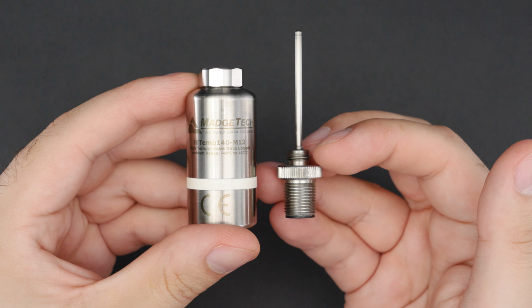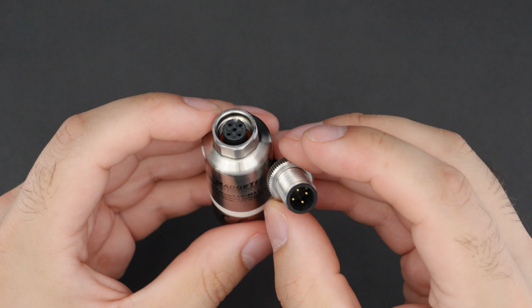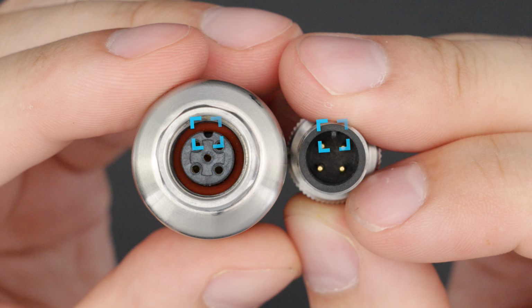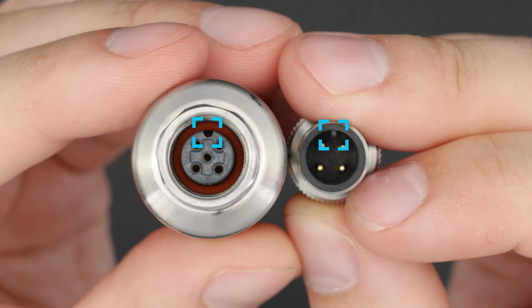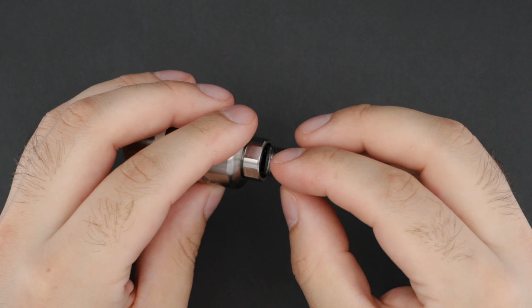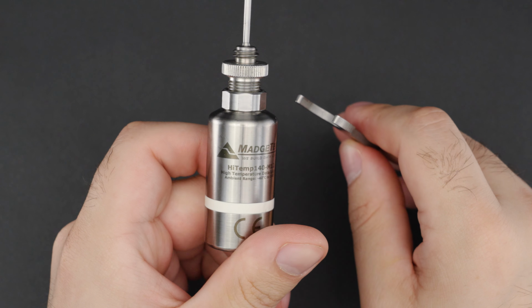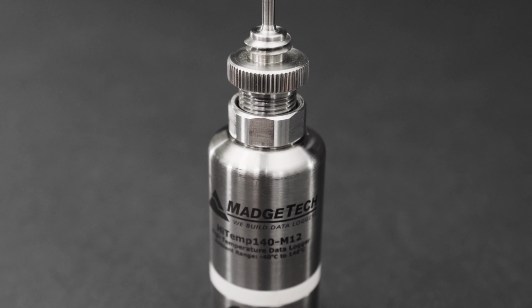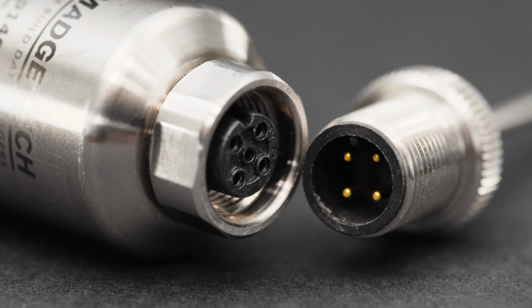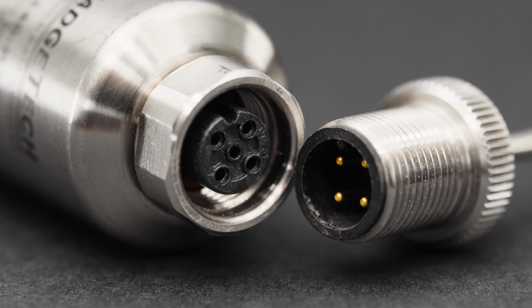Now that everything's gathered, take the logger and probe in hand and line the two ends up using the key on the probe's connection port as a guide. With the probe and the logger loosely joined, fit the 15mm hex wrench to the logger and tighten the connection until resistance can be felt. Make sure not to over-tighten the connection, as doing so could damage the HiTemp140-M12 or the probe.